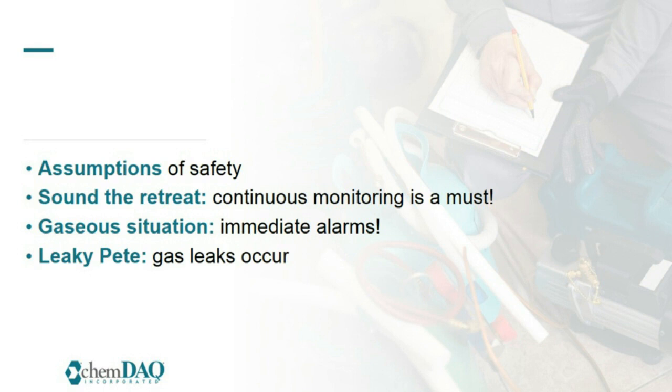Continuous monitoring is a must. This is a gaseous situation. ChemDAQ has installed gas monitoring at several facilities that resulted in the system alarming immediately upon commission.